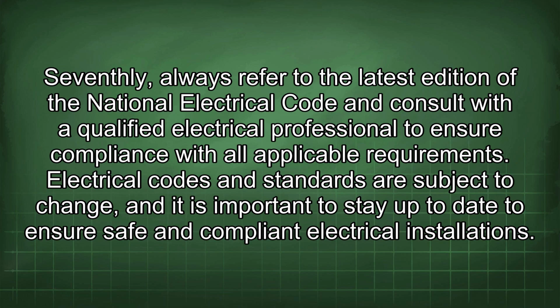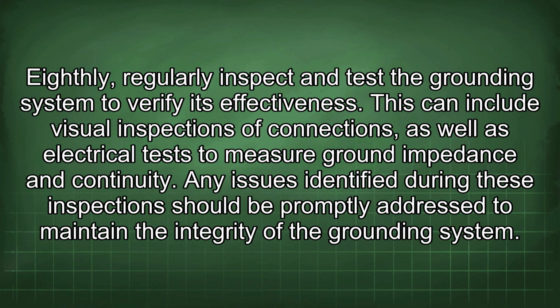Eighthly, regularly inspect and test the grounding system to verify its effectiveness. This can include visual inspections of connections, as well as electrical tests to measure ground impedance and continuity. Any issues identified during these inspections should be promptly addressed to maintain the integrity of the grounding system.